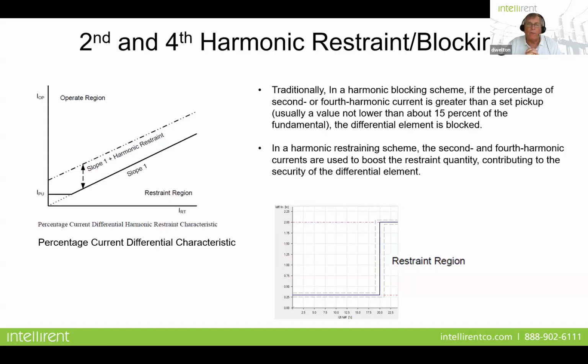Now, let's talk a little bit about second and fourth harmonic restraint and harmonic blocking. One of the phenomena that happens when you energize a transformer is that you're pushing current into the transformer, but it's not coming out yet. So if you don't block the 87 element from tripping one way or another, it's going to nuisance trip as soon as you energize that transformer. So to keep that from happening, they set what's called a harmonic restraint. And what happens when you energize a transformer is you have a certain amount of harmonics, let's say 20-25% harmonic component of that waveform, in both the second and the fourth harmonic restraint.